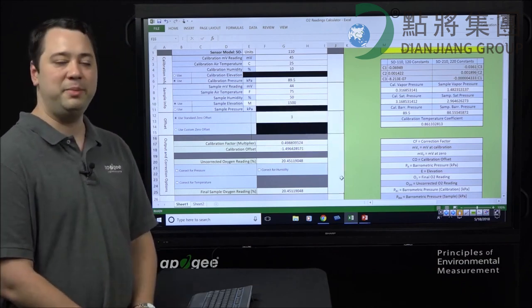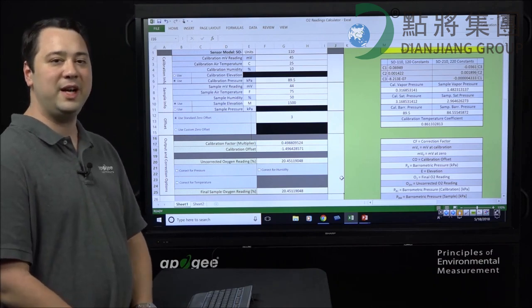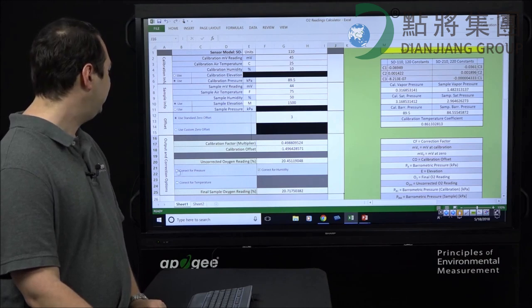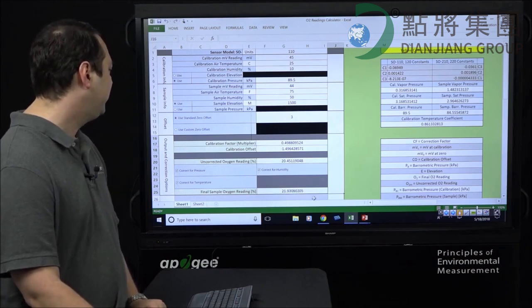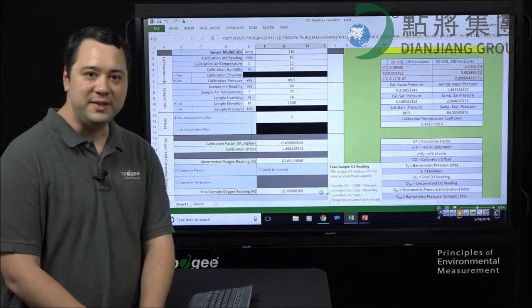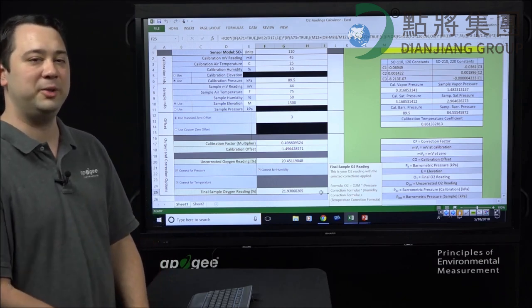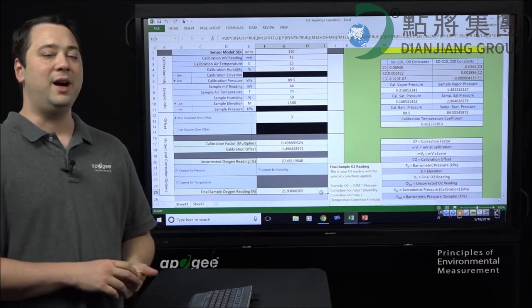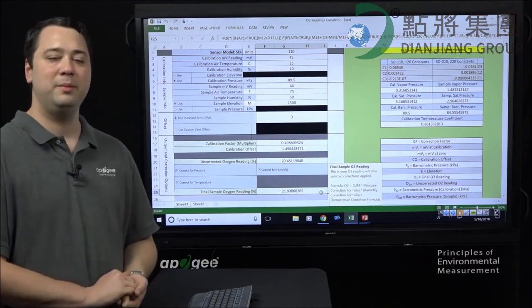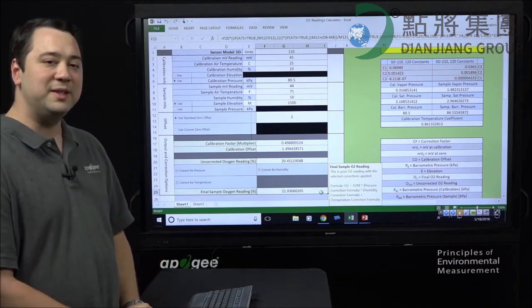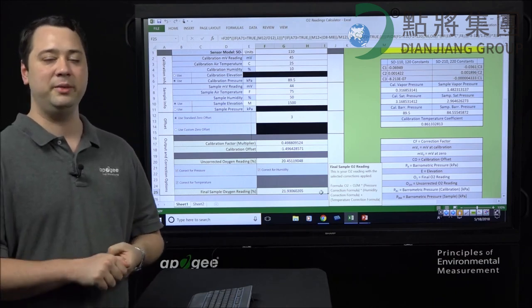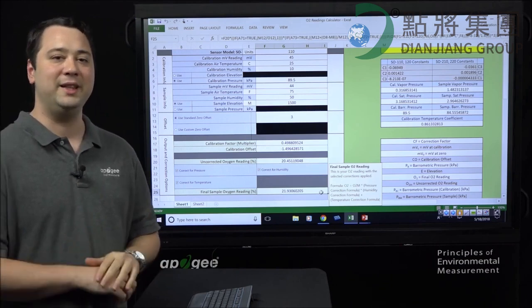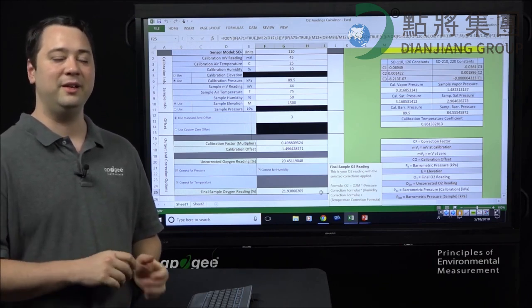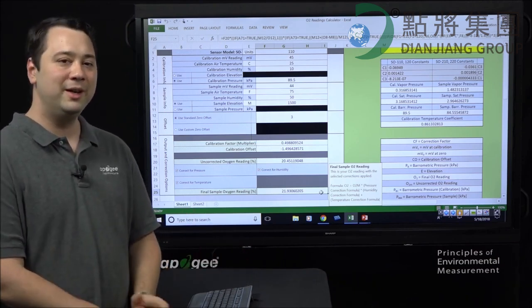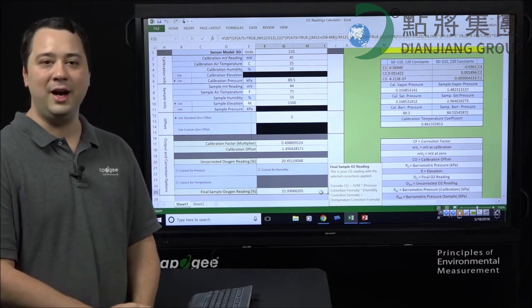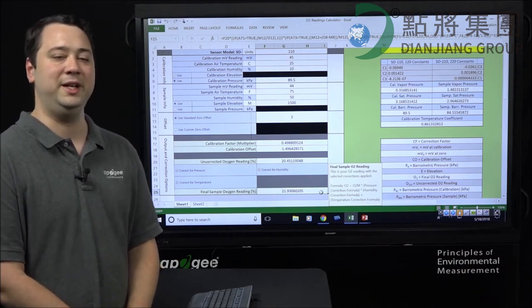And now, to apply corrections based on the information we have entered into this sheet, simply click the check boxes. So let's correct for humidity, let's correct for pressure, and let's correct for temperature. So now, you can see, based on the difference in environmental conditions between the calibration environment and the sample environment, the oxygen reading for our sample environment is 21.9%. Now once again, this is because the temperature, pressure, and humidity have changed between the calibration environment and the sample environment. That's why it's so important to calibrate your oxygen sensor in an environment similar to its sampling environment to minimize the need for these corrections. However, if that's not an option, you can use these corrections to correct your oxygen sensor's readings.